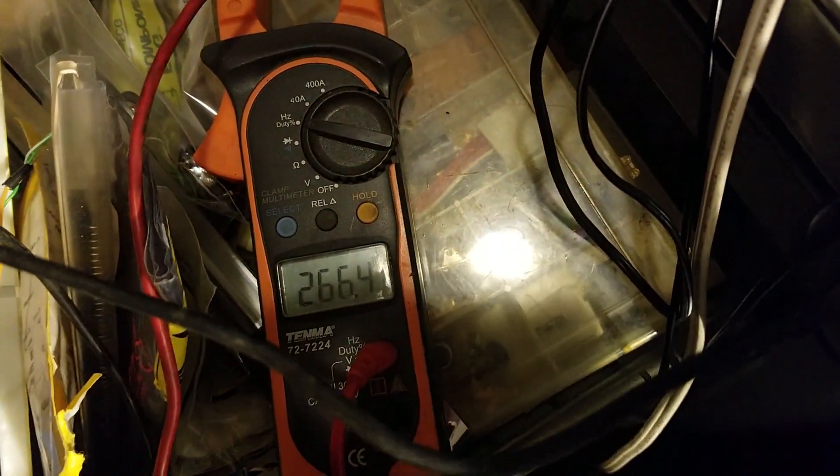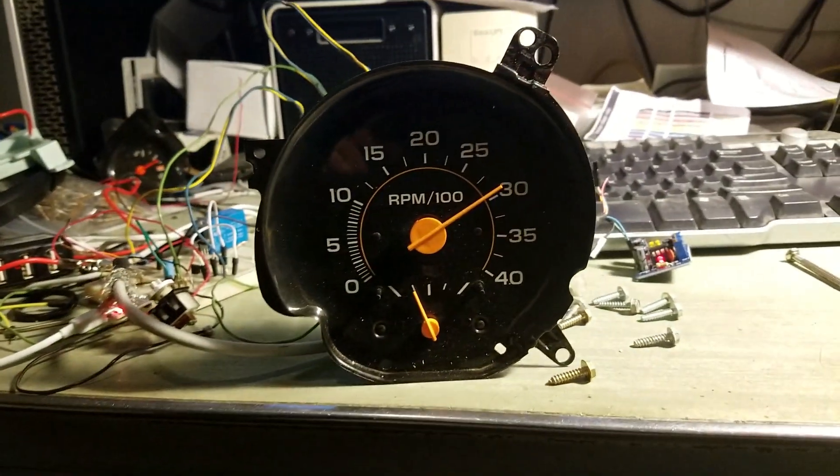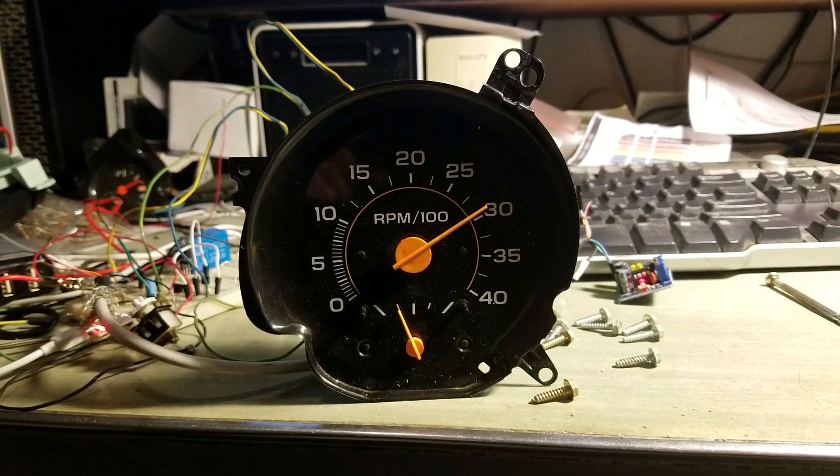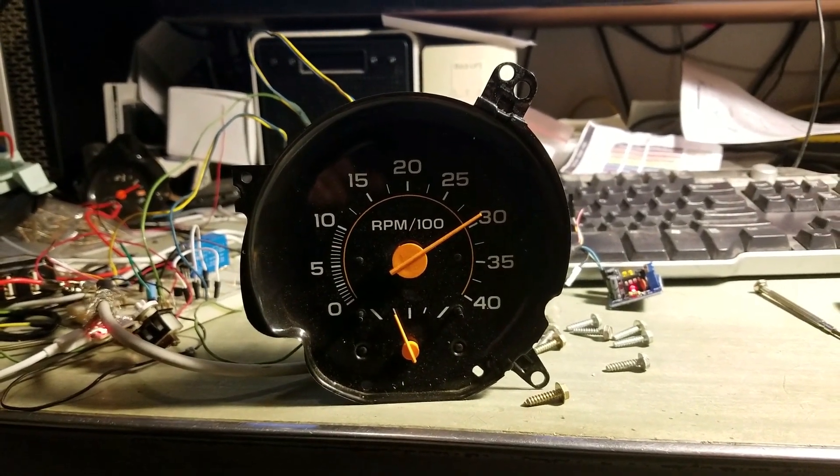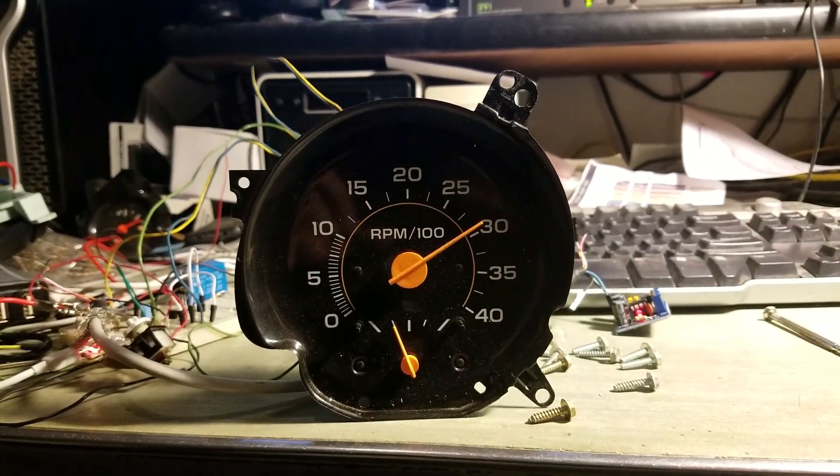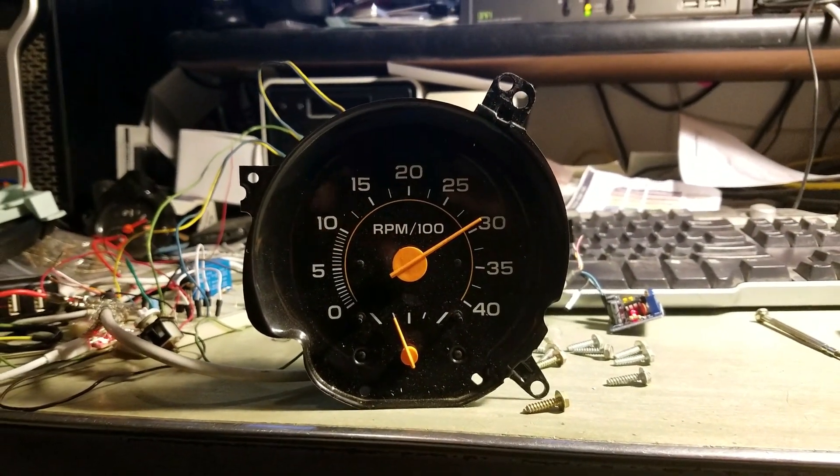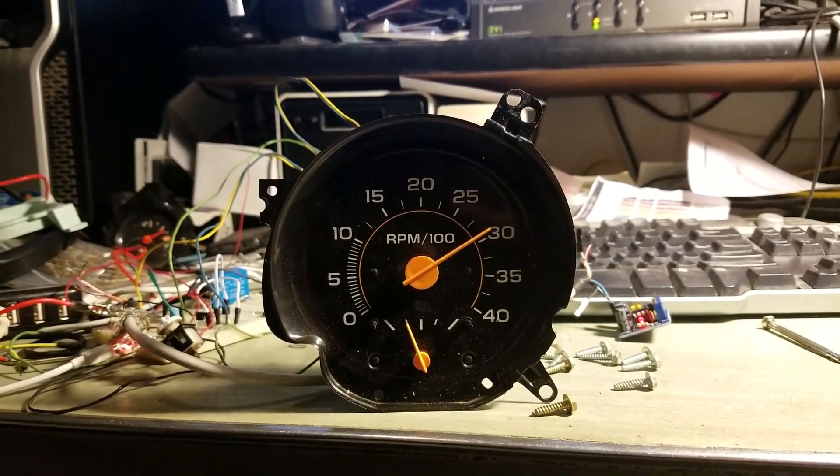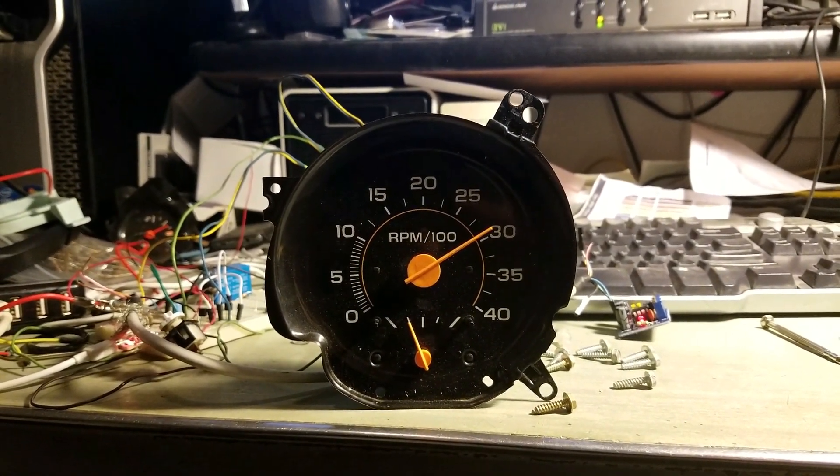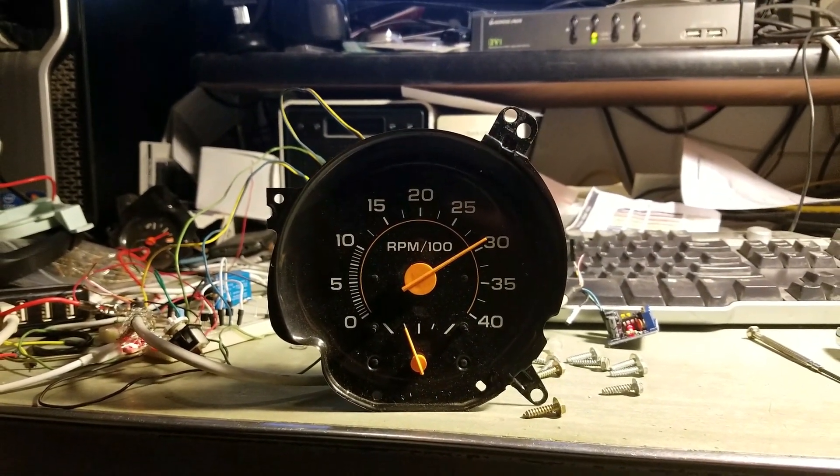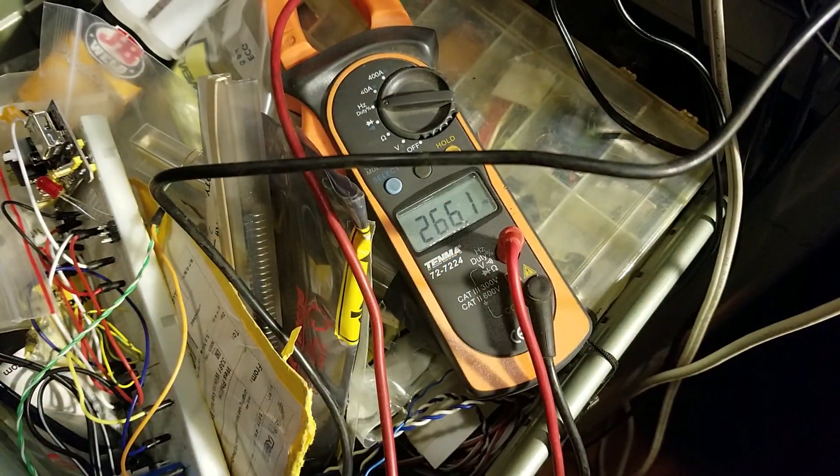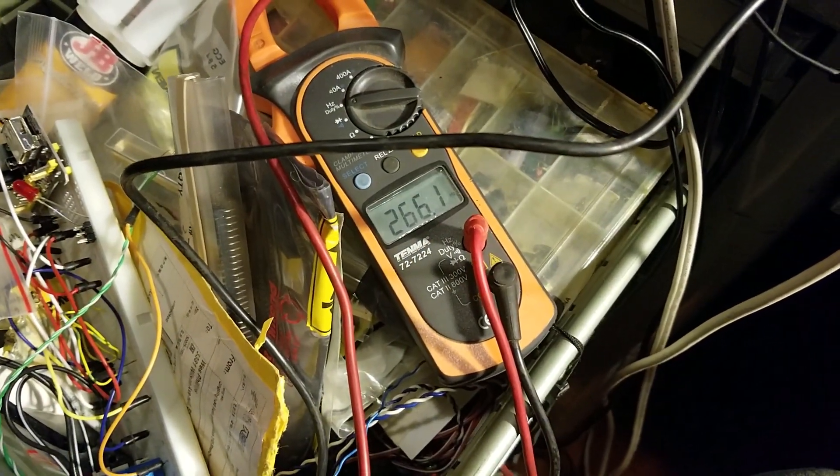So I've got just under that. And with the new chip in there it shows just under 3000, so I need to adjust that until it shows 4000 and then it should be accurate. I'm a little bit low there but now I've got this reading 4000.